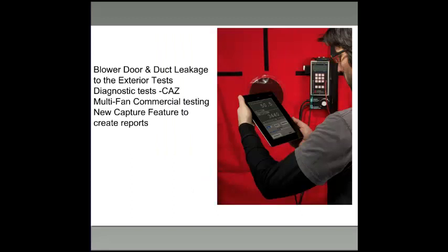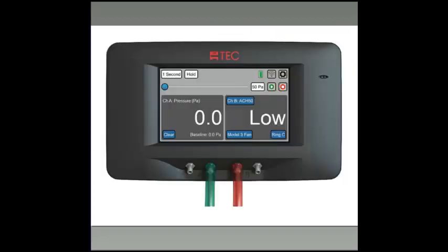Some of the tests you can do, depending on what software you're running, include blower door tests, duct leakage testing, diagnostic testing, and CAZ testing. You can run our multifan software called TechLog 3. And there's also a new feature out right now on Android devices called Capture, which allows you to create reports from your Android device - we'll talk about that a little bit later.